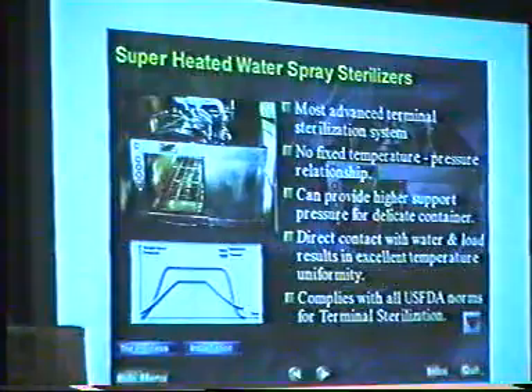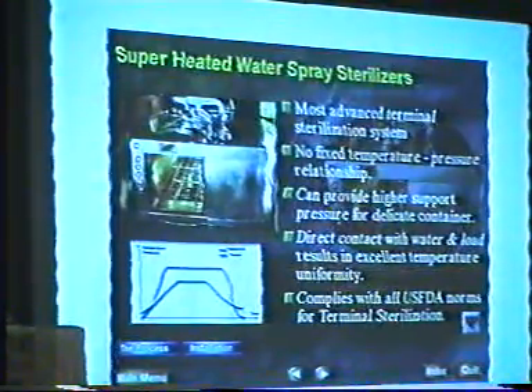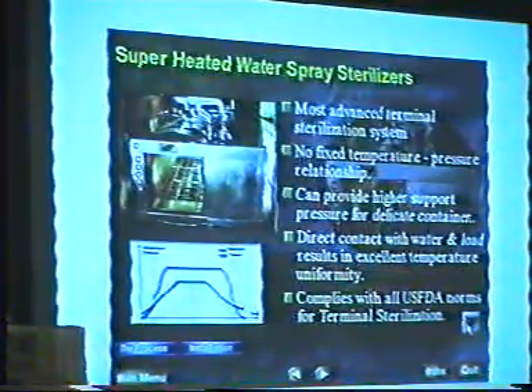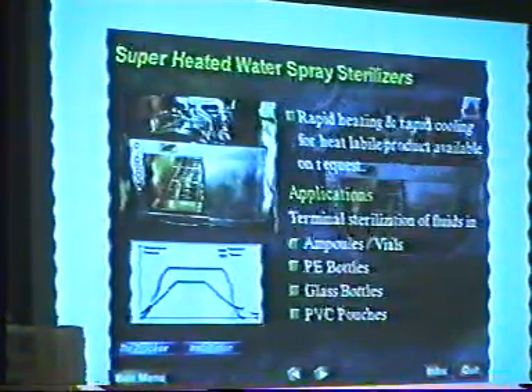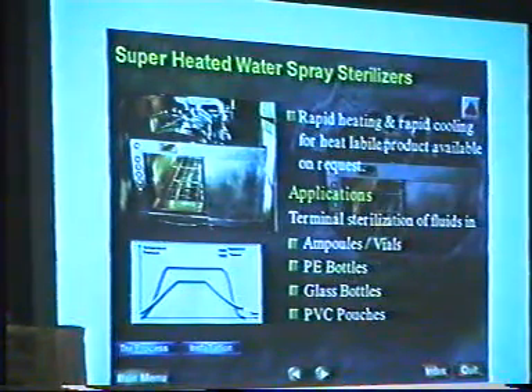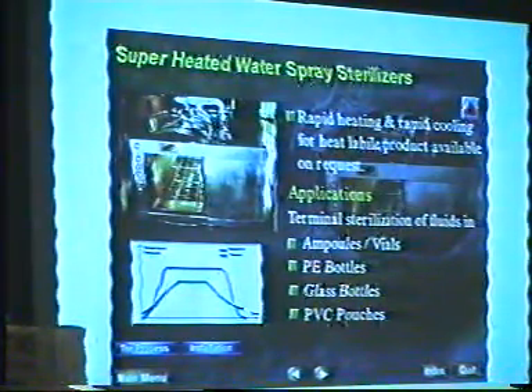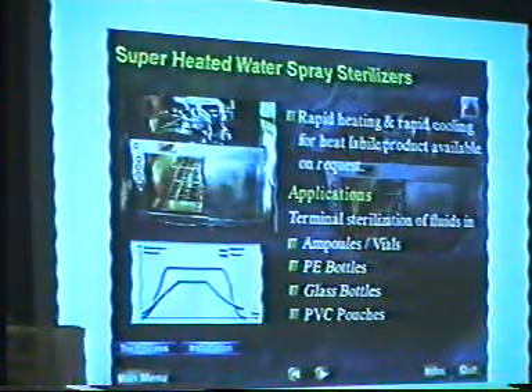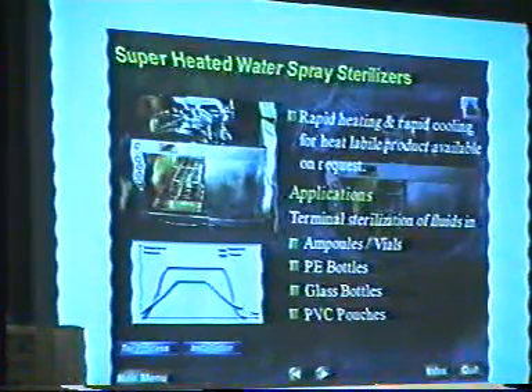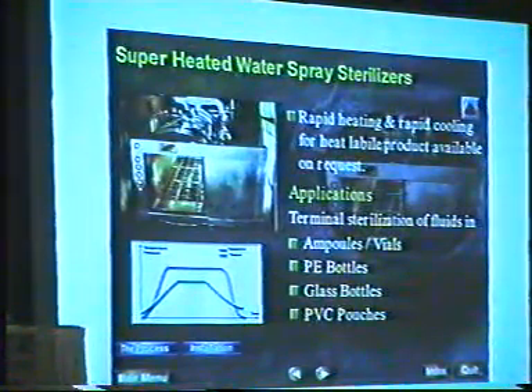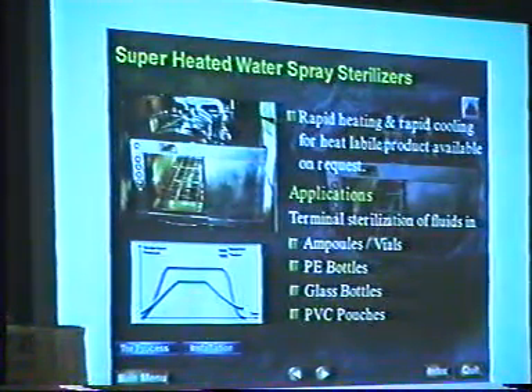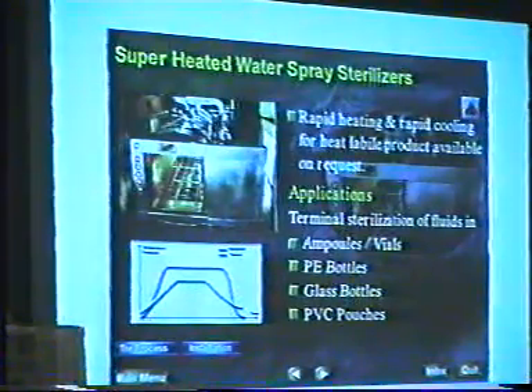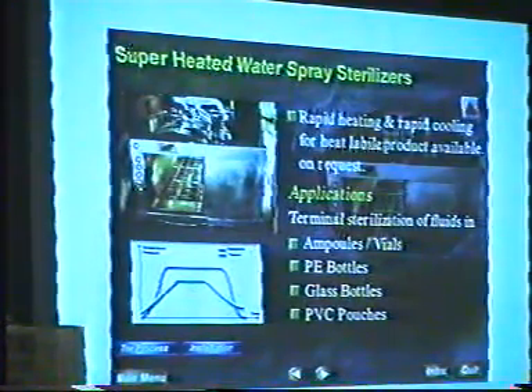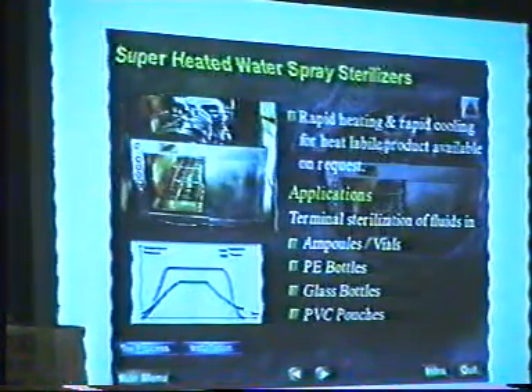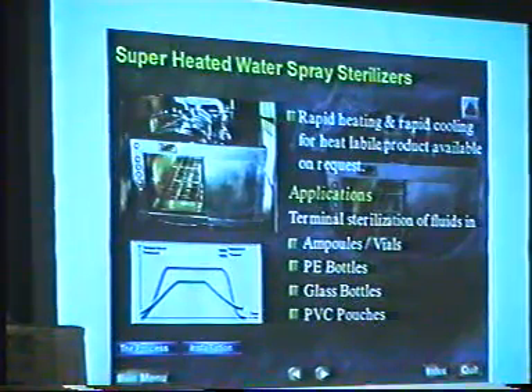Superheated is very, very essential for plastic bottles, which are produced either by blow fill seal machine or by any other method. Superheated you cannot do without when you are doing either pouches or laminates. However, even in glass containers there are many advantages in case you opt for this system, because the closure integrity is guaranteed. The chamber pressure throughout the process is greater than container pressure, so there cannot be any problem.